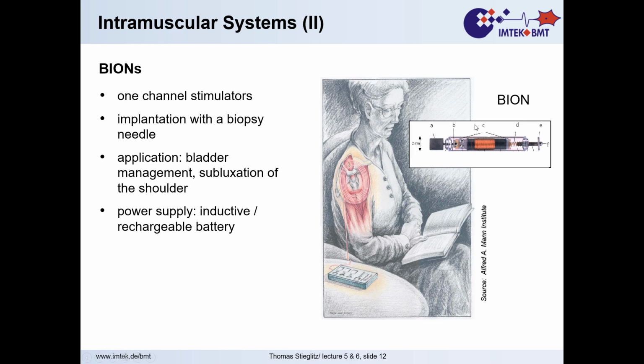Shown here on the edges, the electrodes are connected via wire through that glass pearl as a hermetic seal to the implant, and it broke here. If you remember vaguely your micromechanics, and your mechanics and a bending beam, then you would have maximum force at those transitions there. And that was a showstopper. They had to change that. They improved that, and I'll tell you the real showstopper at the end of that.